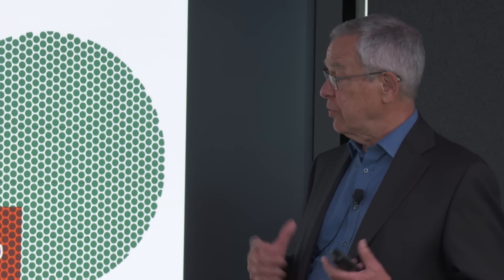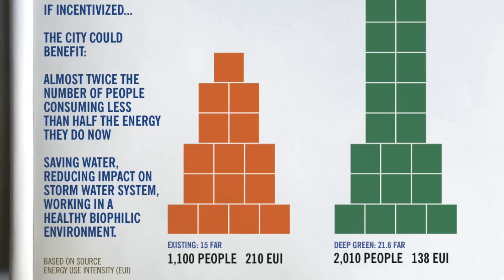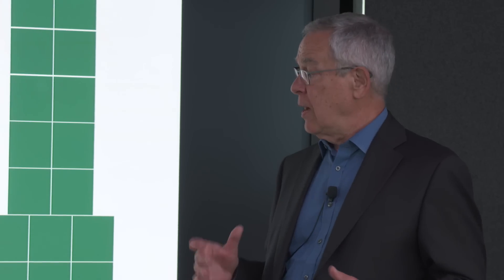When we did our analysis, the building we looked at had 1,100 people and used a certain amount of energy. We could put almost twice the number of people in the new building and use less energy. Here's the trick: 1,100 people at 210 EUI versus 2,000 people at 138 EUI. If this could happen — and it's certainly not going to happen in all of these buildings, which are not only in midtown but also in lower Manhattan — if you took a certain percentage of them, added some additional floor area, and made them seriously green, you might have something. That's our hope.